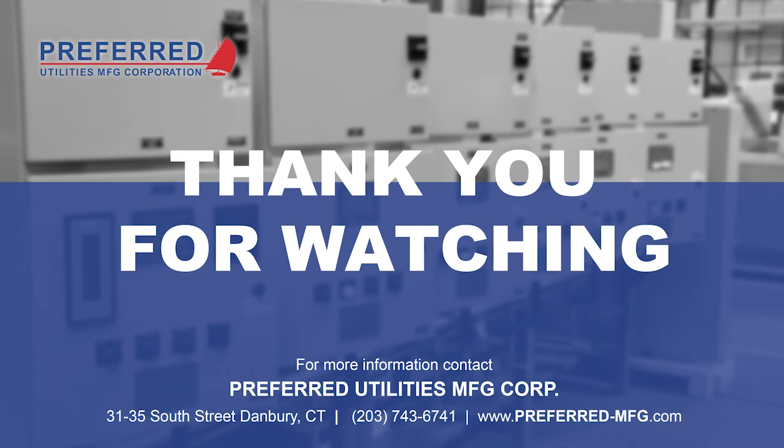So they are the most vulnerable part of a fuel system, and heat tracing and insulating those lines is an inexpensive way to protect the most vulnerable part of a fuel system. And one thing I learned in 2021, the first day that cold front came in, we had temperatures in the low 20s, and I had a customer saying they had gelled fuel. And diesel fuel typically gels at 18 degrees, and we hadn't gotten that cold yet. We were going to in a day or two, but we hadn't gotten that cold yet.